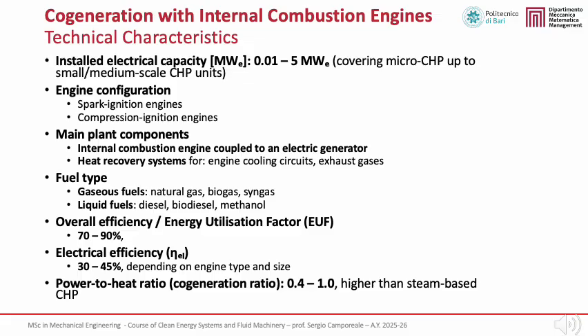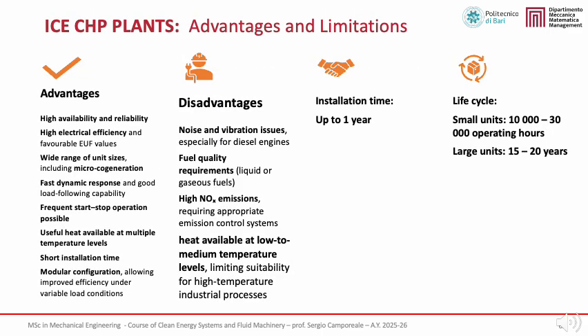ICE CHP plants can operate on a wide range of fuels, including natural gas, biogas, and syngas, as well as liquid fuels such as diesel, biodiesel, or methanol. Overall efficiencies, expressed through the energy utilization factor, typically range between 70 and 90%, while electrical efficiency alone reaches values of 30 to 45%, which are particularly high for decentralized generation systems. The resulting power-to-heat ratio between 0.4 and 1 is generally higher than that of steam-based CHP systems. Finally, let us summarize the main advantages and limitations of ICE-based CHP plants.